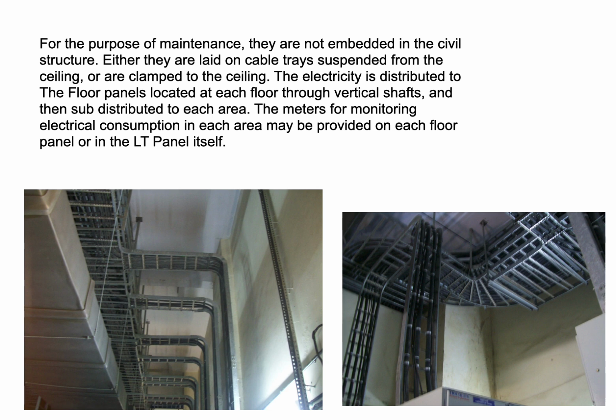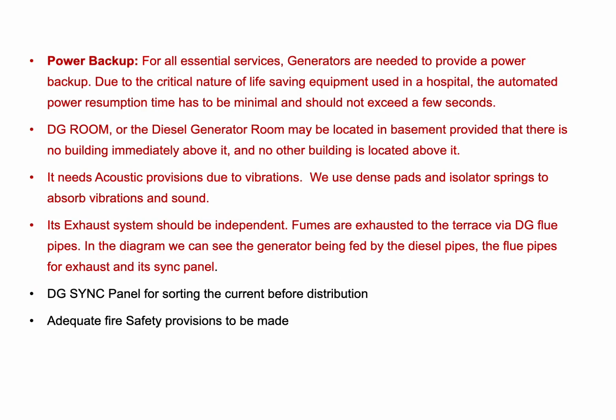Generators are needed to provide a power backup. Due to the critical nature of life-saving equipment used in a hospital, the automated power resumption time has to be minimal and should not exceed a few seconds. The DG room or the diesel generator room may be located in the basement, provided that there is no building immediately above it and no other building is located above it. It needs acoustic provisions due to vibrations.